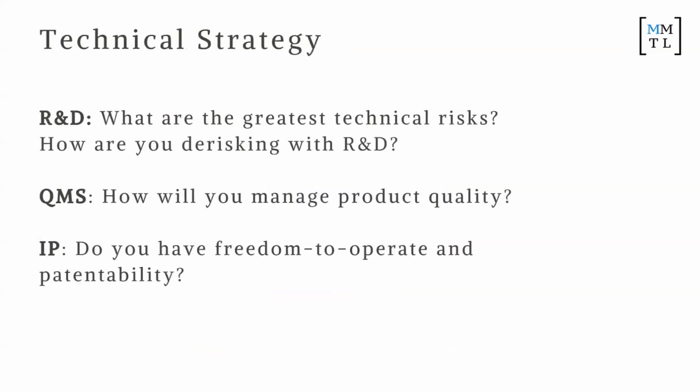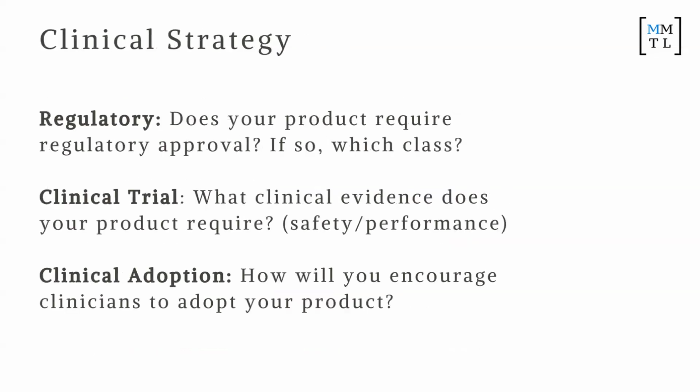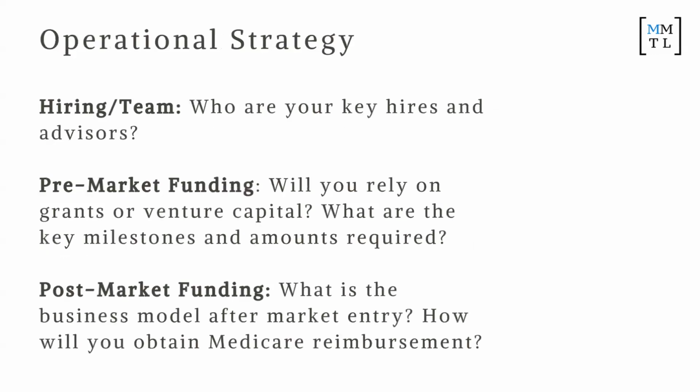Now, historically, this one has been the most challenging by far, right? Which is, how do you get regulatory approval? We'll go through again what that means, which is you need to actually get permission from the FDA, TGA, or CE mark, depending on which geography you're in, to sell your device. For the vast majority of medical devices, you need permission before you can sell. The only way to get that permission is through clinical trials, which demonstrate that it's safe and effective. So historically, that's been the biggest concern.